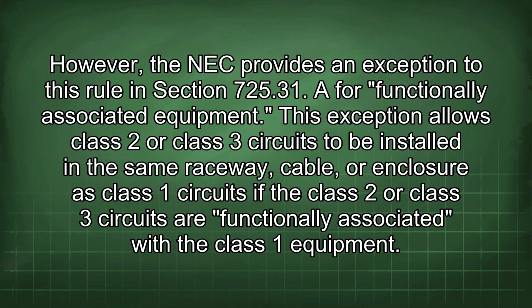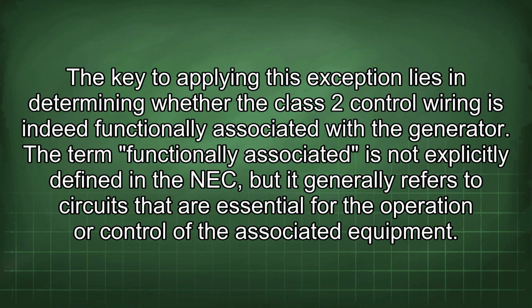This exception allows Class 2 or Class 3 circuits to be installed in the same raceway, cable, or enclosure as Class 1 circuits if the Class 2 or Class 3 circuits are functionally associated with the Class 1 equipment. The key to applying this exception lies in determining whether the Class 2 control wiring is indeed functionally associated with the generator. The term functionally associated is not explicitly defined in the NEC, but it generally refers to circuits that are essential for the operation or control of the associated equipment.